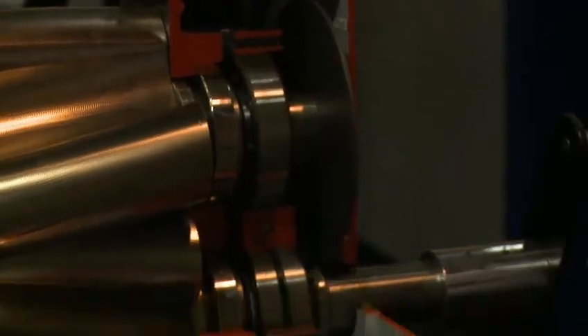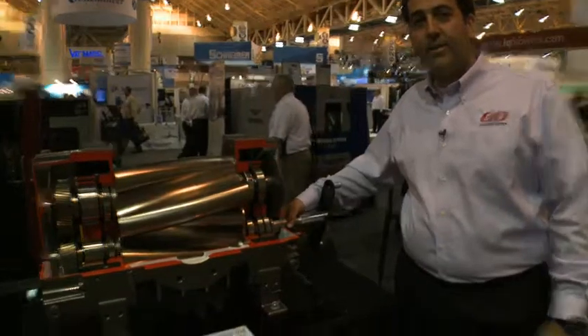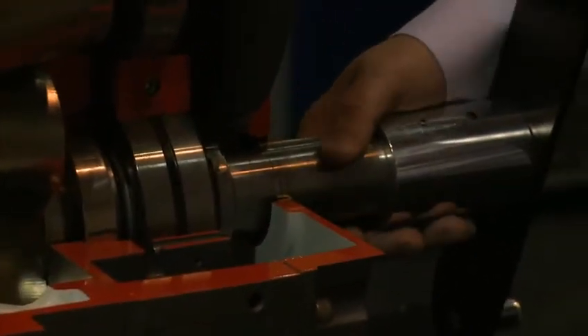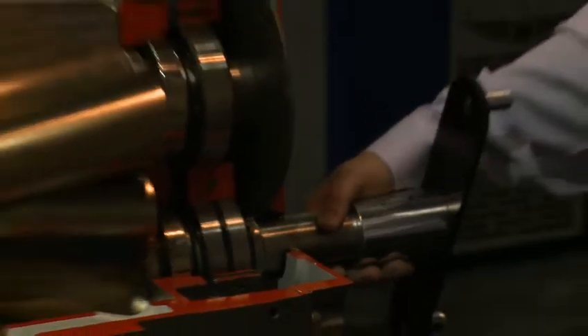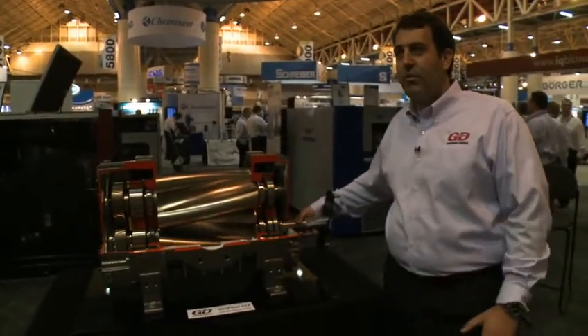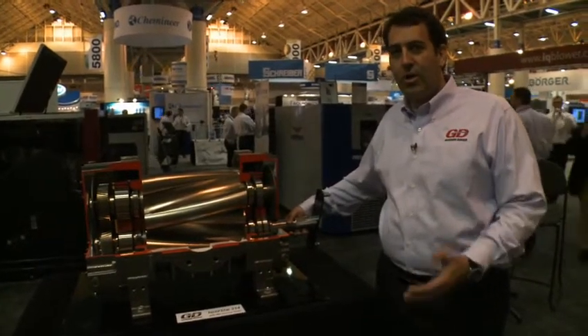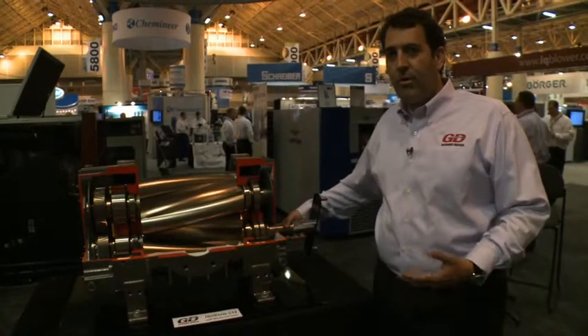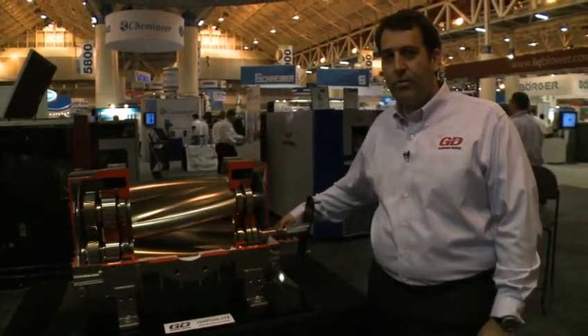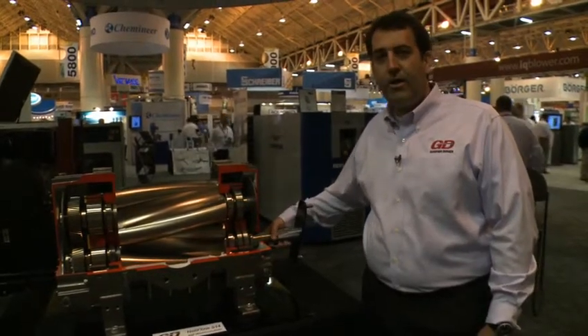It's also a very robust machine. We've used cylindrical roller bearings on the drive, along with a robust thick shaft. That has allowed us to have great overhung load capabilities over our competition. So when you replace a competitor brand with this machine, or you have a new blower package, you can be assured that the machine is going to last a long time. Most PD blowers are belt driven because of flow and pressure requirements, to be precise. And this machine within the HeliFlow line is very robust.